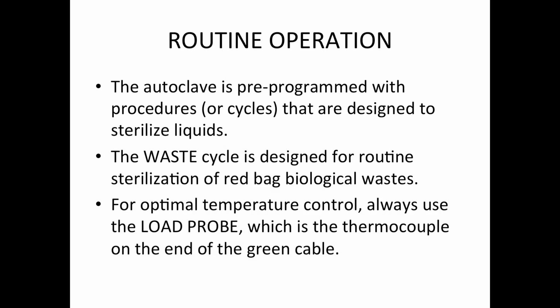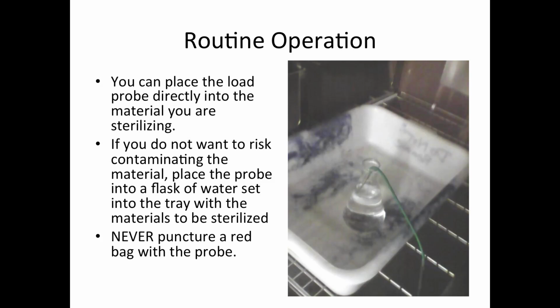When you step up to use the autoclave, remember that it is pre-programmed with procedures or cycles that are designed primarily to sterilize liquids. You can, of course, use them to sterilize solids or wastes. The waste cycle, for instance, is designed for the routine sterilization of red bag biological wastes. And we have what's called a load probe in the autoclave. It's the little thermocouple on the end of the green cable, and that will go into your load or your media or whatever it is you're sterilizing and give you very accurate temperatures. So you place the load probe directly into the material you want to sterilize. But if you do not want to risk contaminating your material, place the probe into a flask of water set into the tray next to the materials to be sterilized, and never puncture a red bag with the probe because you want to see how hot it got inside the bag. That's what the autoclave tape is for.